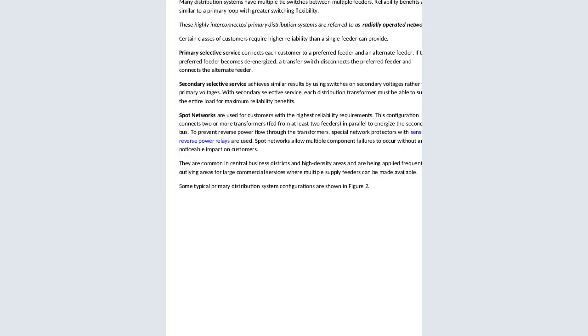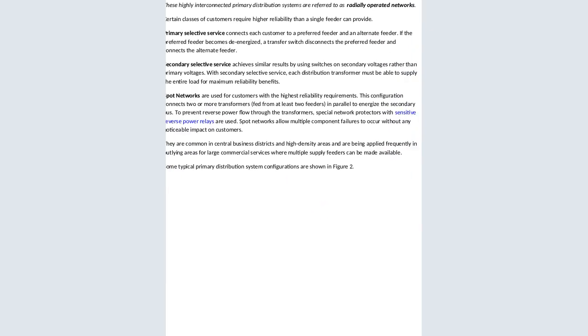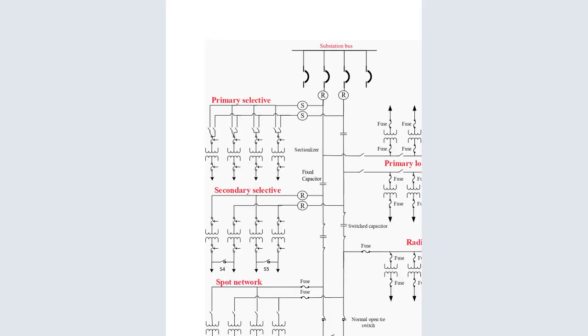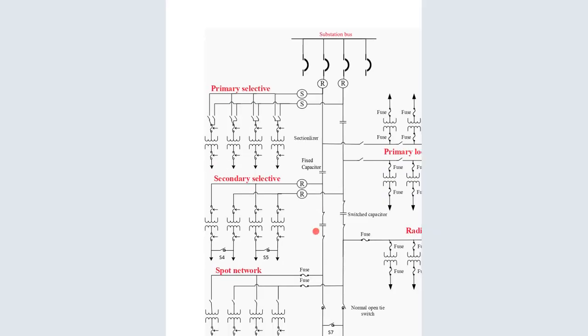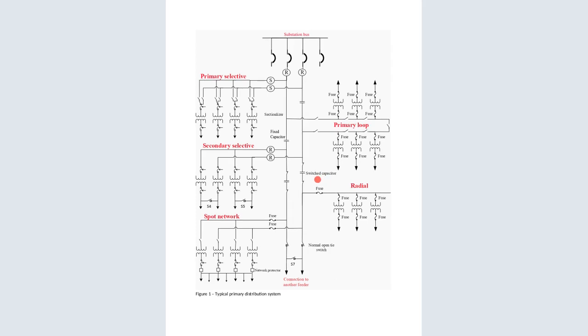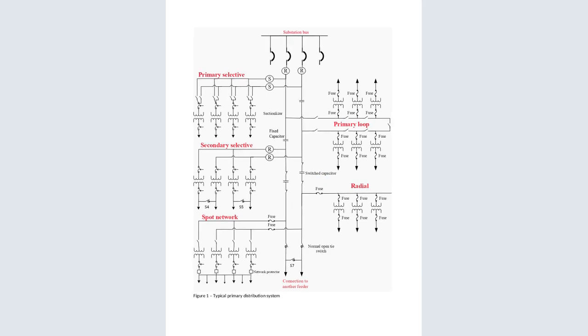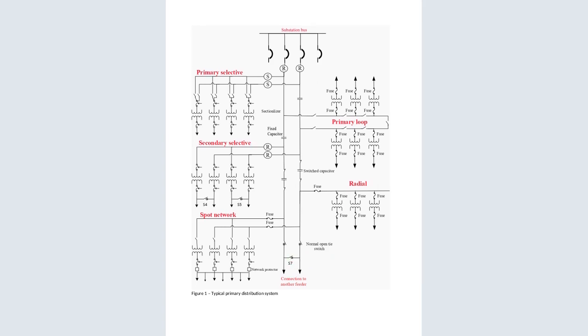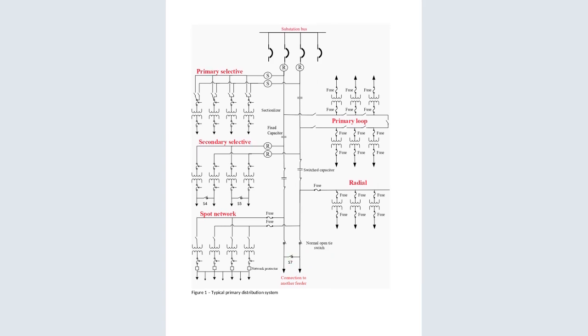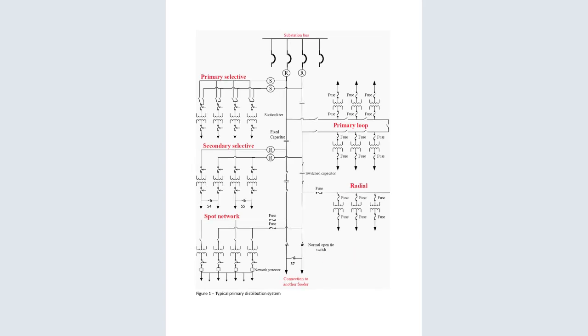Some typical primary distribution system configurations are shown in the next figure. You can now see that figure. Now we have a substation bus, primary selective. You can see it's the first one to tap power. Then we come to the secondary selective, then the spot network. And then the primary loop is there and the radial is there. The radial is the last because it's the most interrupted one, and this one now goes to the rural areas.